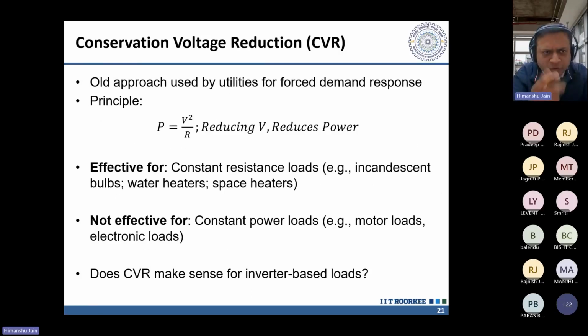One example I'll talk about is conservation voltage reduction. If anybody has been in the utility business for the last two to three decades, they may recognize that conservation voltage reduction has been used for three to four decades by utilities to force demand response. They would change the voltage right at the substation. The voltage goes down, and since a lot of our loads used to be simple resistive loads—think of your incandescent bulb of the past, or water heaters, space heaters—when voltage goes down, you get a power reduction in the square of the voltage terms. So it was pretty effective, and people used it quite effectively in the past.